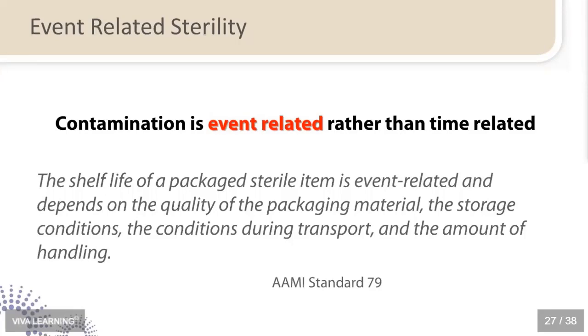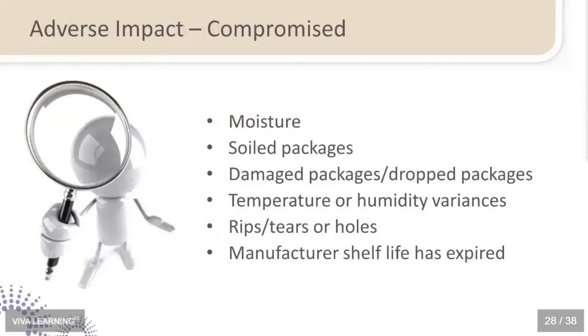And sometimes you'll see this abbreviated ERS, event-related sterility. Again, this should be designated in your infection control manual as to the protocol, because that's part of your stock rotation protocol. So what are some of those adverse things that can happen? I sort of gave you a list a moment ago. The package becomes wet or soiled, if it's damaged or dropped, if you have extreme temperature or humidity variances. If you are part of a mobile clinic and you're putting the instruments into your car and taking them from one place to another, cars get very hot very quickly in the summertime, and that could be a contraindication and impact that you went beyond the 70-degree temperature, or 70% humidity. So you need to think about those things when transporting.